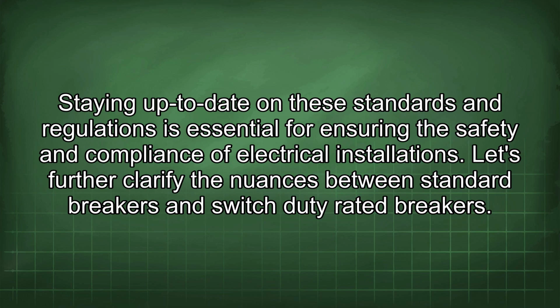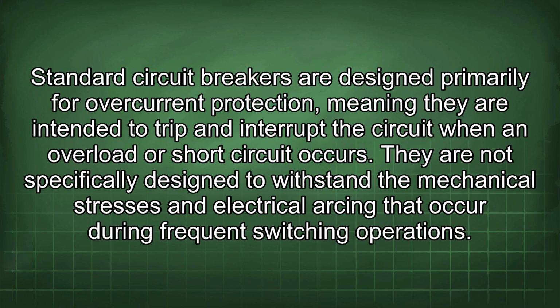installations. Let's further clarify the nuances between standard breakers and switch-duty rated breakers. Standard circuit breakers are designed primarily for overcurrent protection, meaning they are intended to trip and interrupt the circuit when an overload or short circuit occurs. They are not specifically designed to withstand the mechanical stresses and electrical arcing that occur during frequent switching operations.